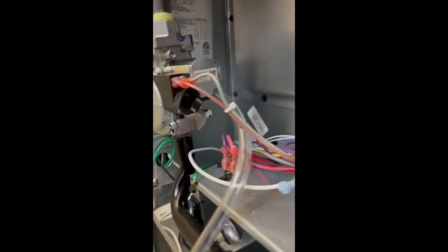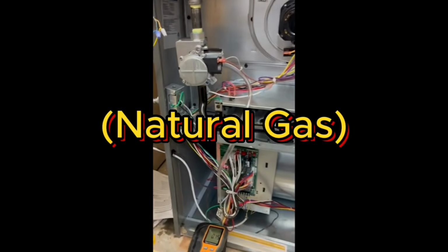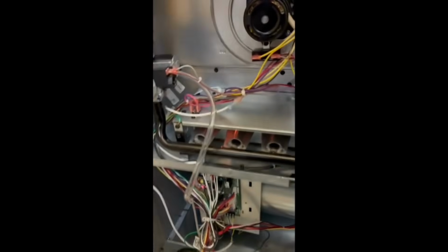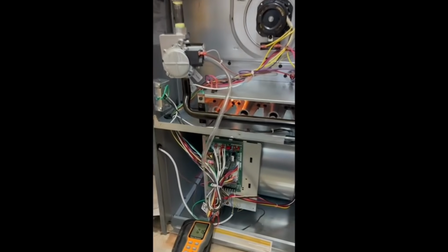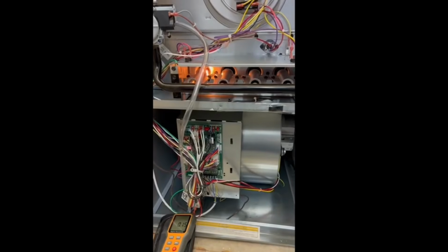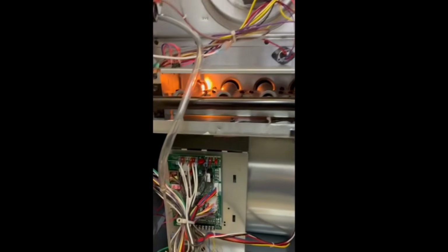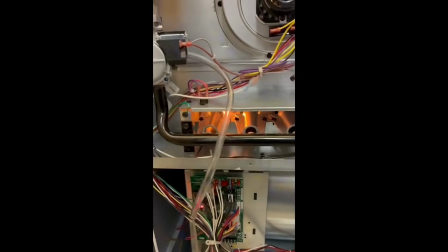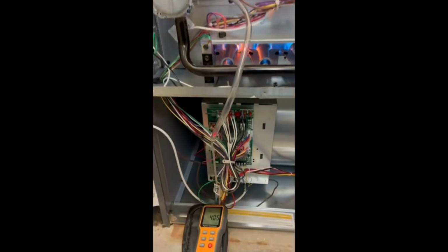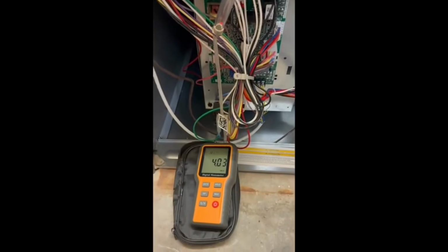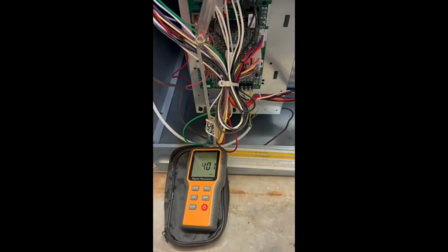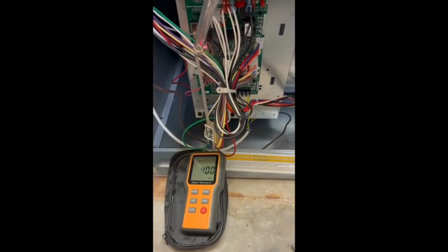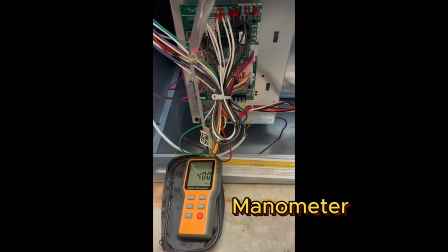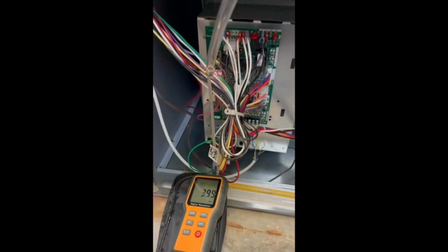Okay, and then now I'm going to check the outlet gas pressure. And we want it to be around, or ideally at, 3.5 inches water column. So we have to check that when the unit starts and runs, and adjust it in real time if need be. See, the hot surface igniter is glowing. The gas valve should open. And the burner should light. There we go. So you can see we're a tiny bit high. I want to let it settle out here for a few minutes, but it looks a little bit high. So again, I want that down around 3.5 inches of water column.